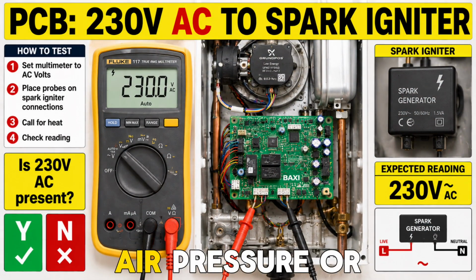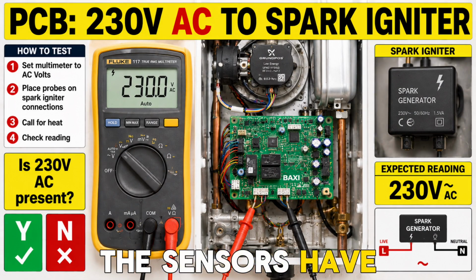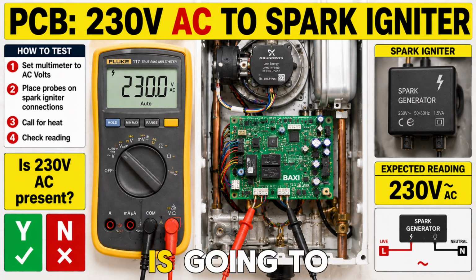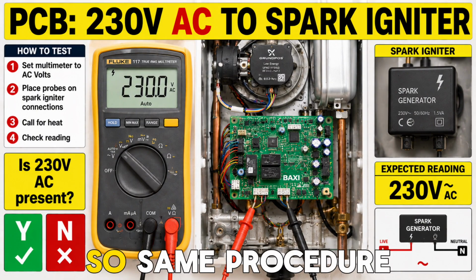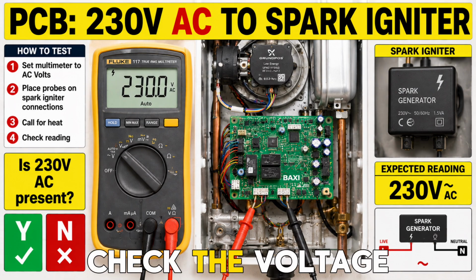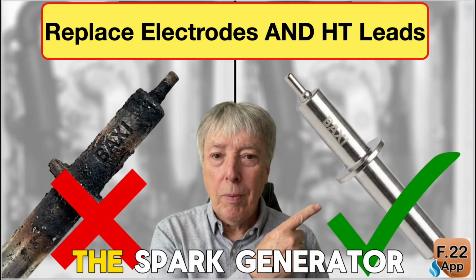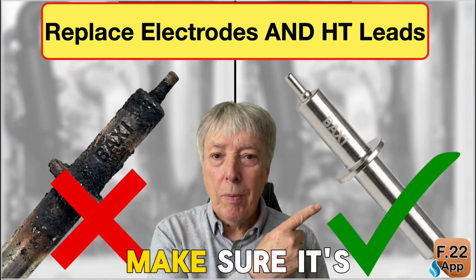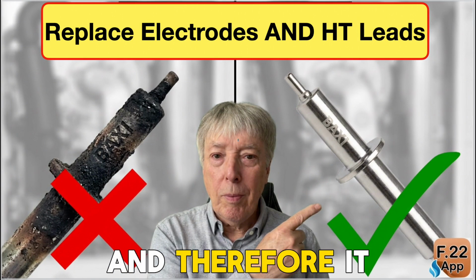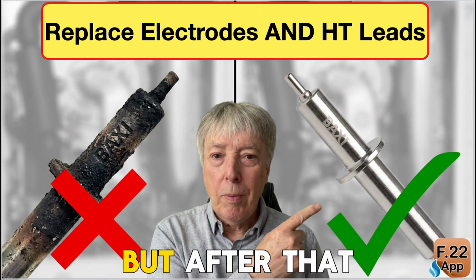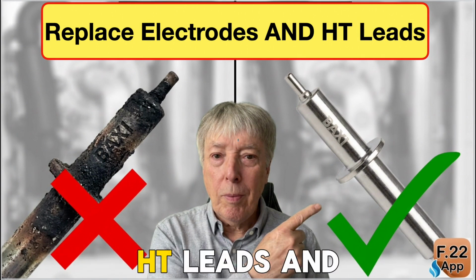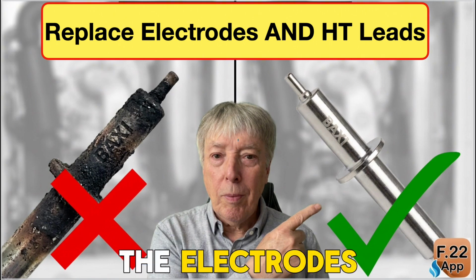So after the air pressure or the sensors have okayed it, the next stage is going to be the spark igniter. So same procedure, check the voltage on the PCB, check it at the spark generator, make sure it's arrived, and therefore it should start sparking. But after that, we're going into HT leads and the electrodes.